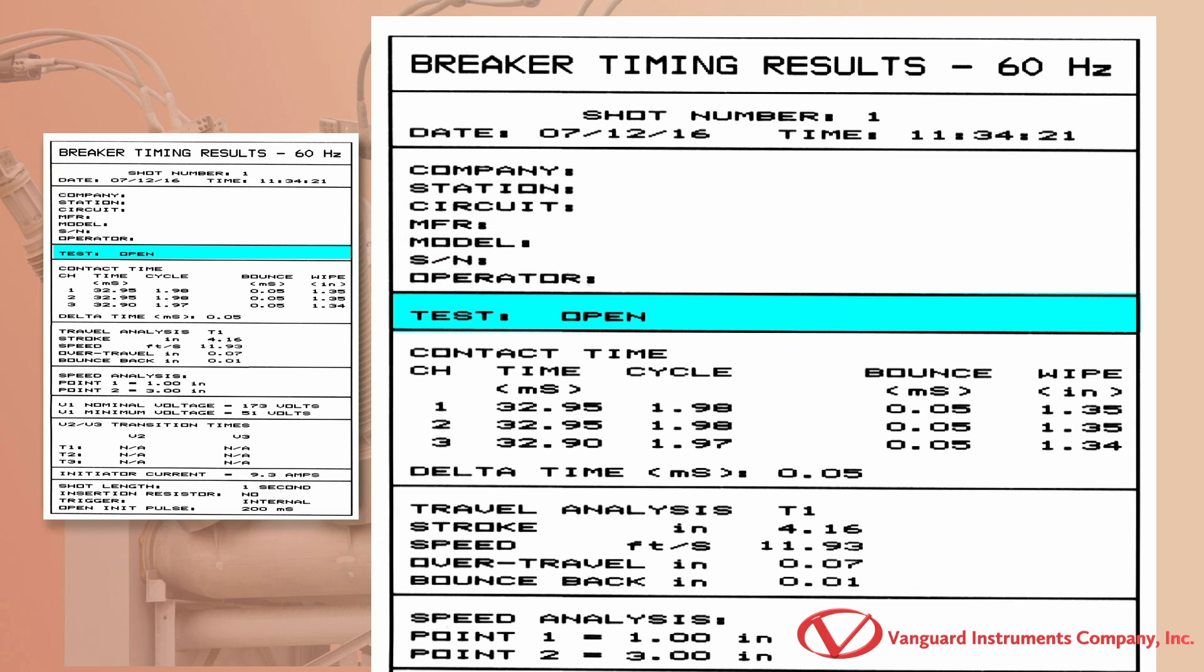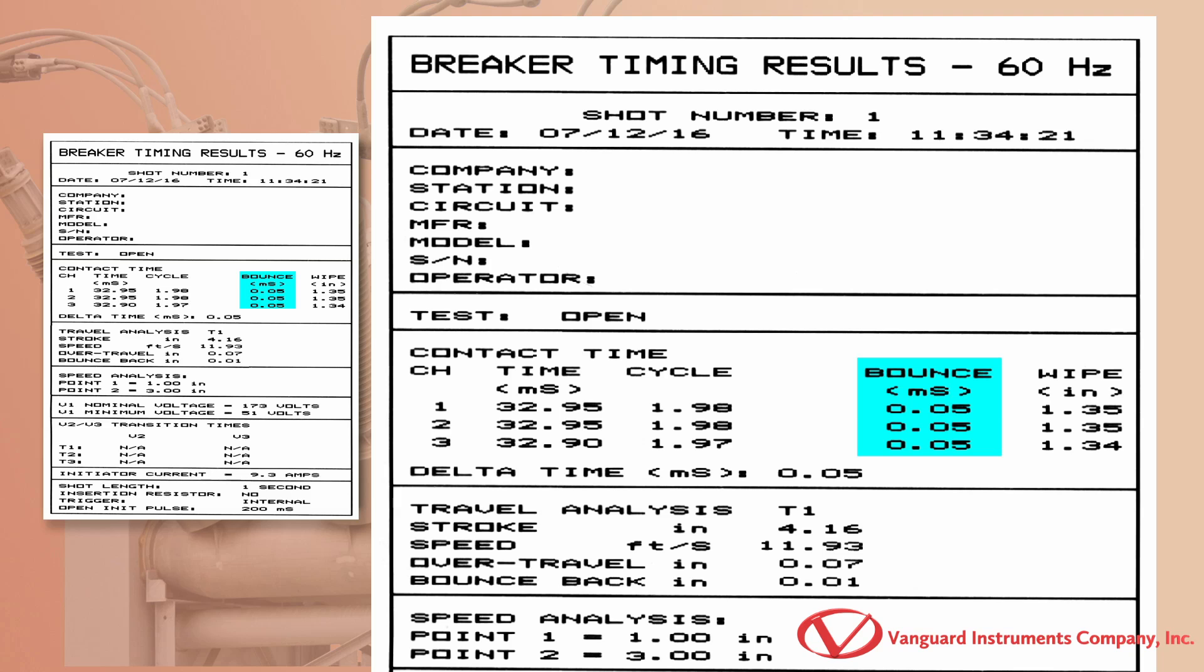The test type is shown in this section. In this case, we can see that the results are from an open test. The contact times are shown here in milliseconds. The equivalent times in cycles are shown in the cycle column. The measured contact bounce duration is listed here in milliseconds.